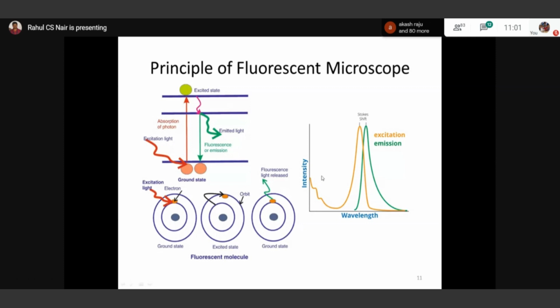This is the typical arrangement for a fluorescent microscope, and here you can see we have a light source, and for the light from the light source we put a special filter, because our fluorescent dye may be sensitive to, here, green colored light is shown. So this filter passes only the green light, and whatever dye is used with the sample is also sensitive to that particular wavelength. It is focused onto the specimen, and the emitted light comes directly to the eyepiece or the sensor. Here is the optics piece called a dichroic mirror. On the right side you can see a filter cube, an actual view of the filter cube, and you can selectively pass light through a filter cube, right? So the excitation light can flow like that, and it cannot go backward to the eyepiece or to the camera.